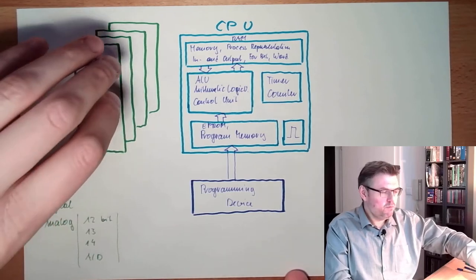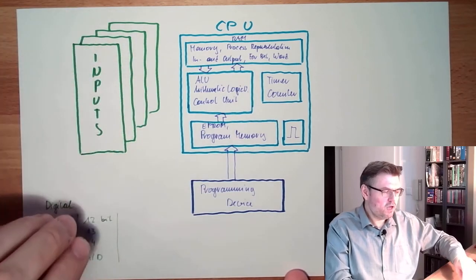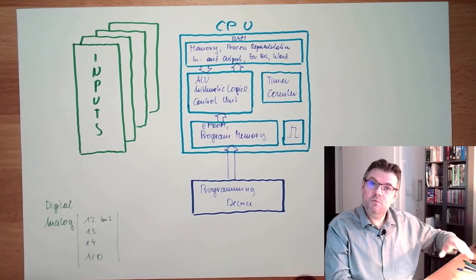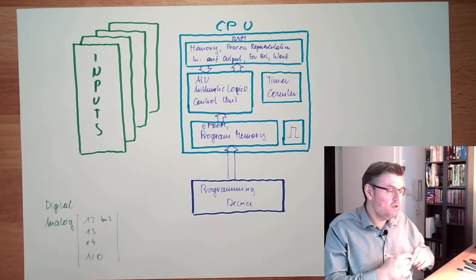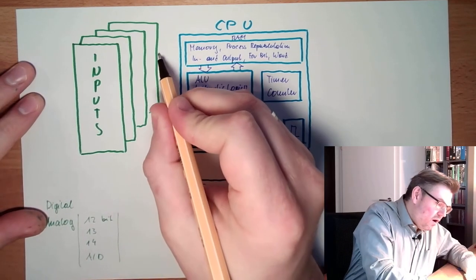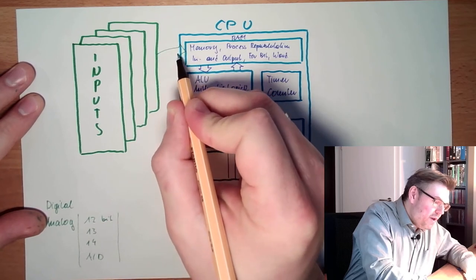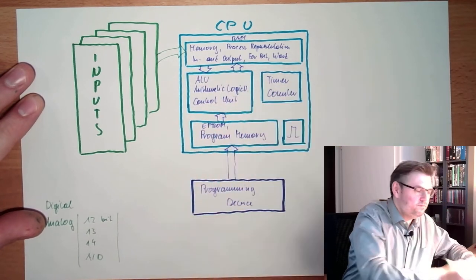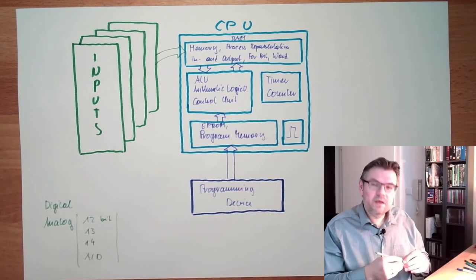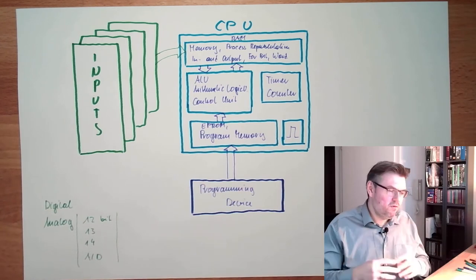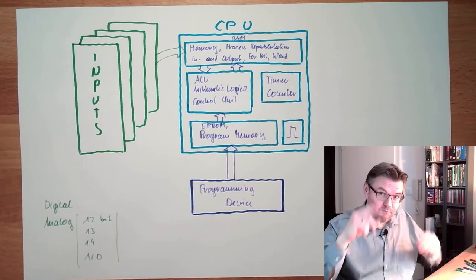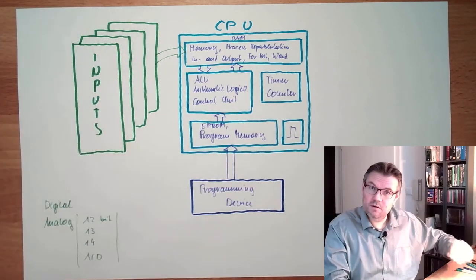So if this is really an issue in your application, then you have to spend a little bit more money for a more expensive card. Then it's working in parallel. So here we have some inputs, digital inputs 0s or 1s with a certain voltage level, or analog inputs with a certain value. These inputs are now, in first step, transferred to the memory, a so-called input process representation, a snapshot of the inputs, like a picture.